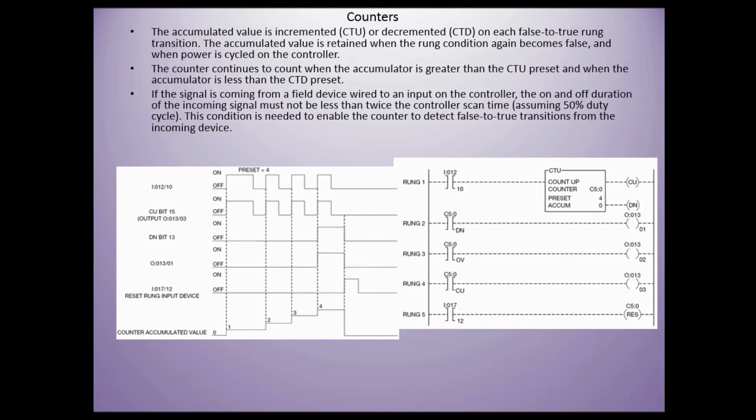The cumulative value is incremented on the CTU or decremented on the CTD on a false to true rung transition. Whatever the logic is in front of that counter has to go from false to true in order to count one up. If it just stayed true the whole time, it wouldn't keep counting like a timer would. You have to see that false transition happen.